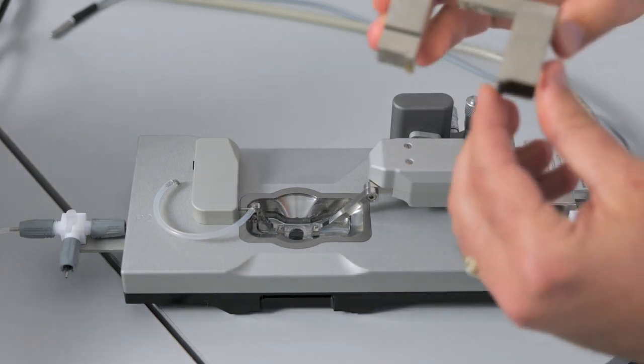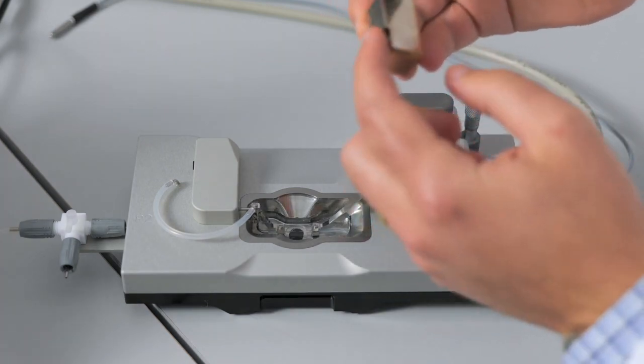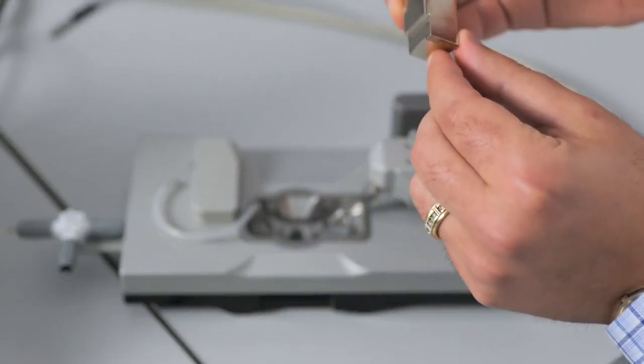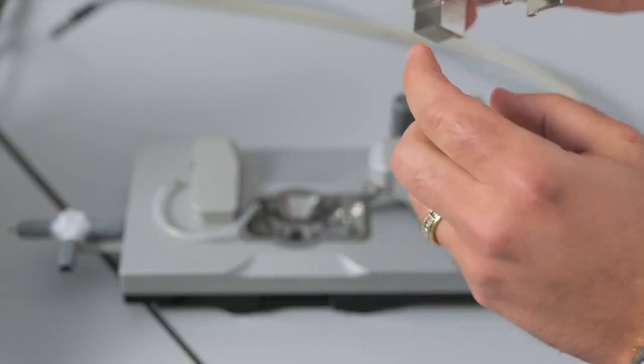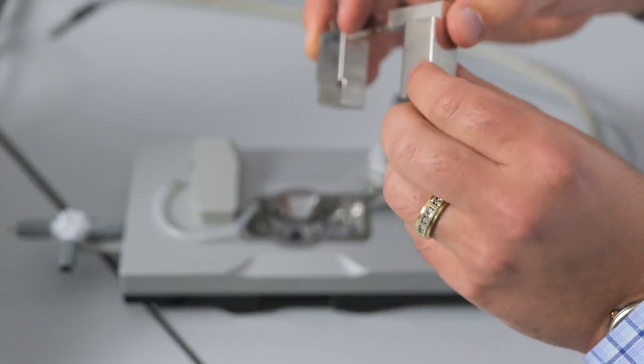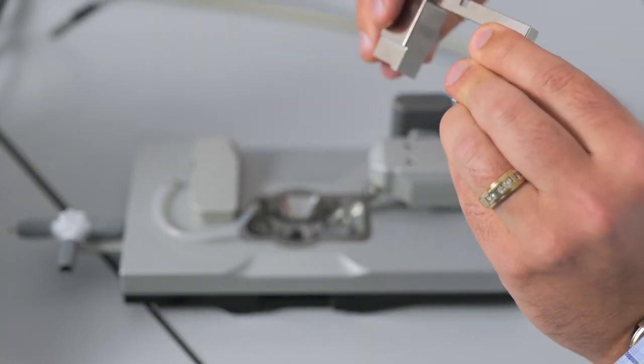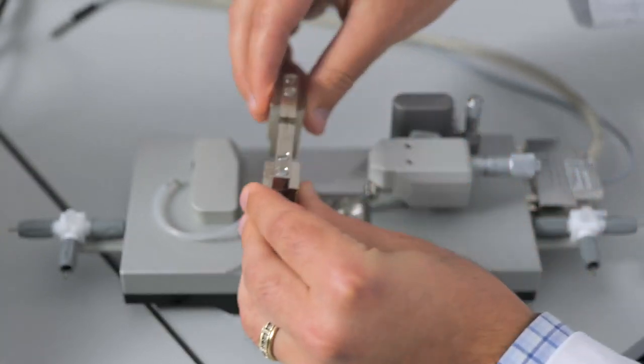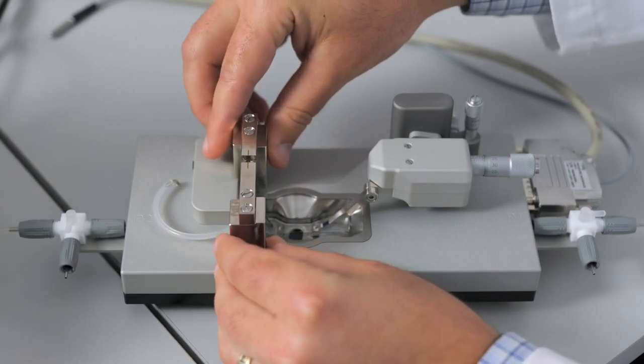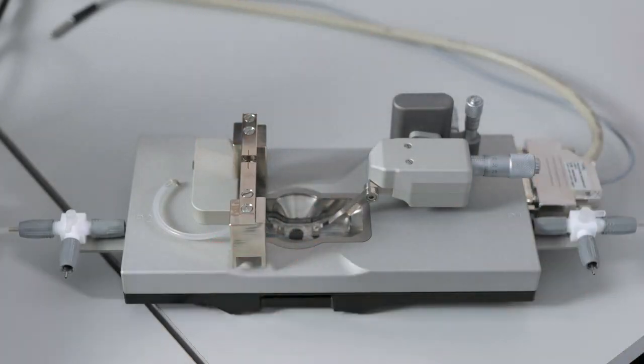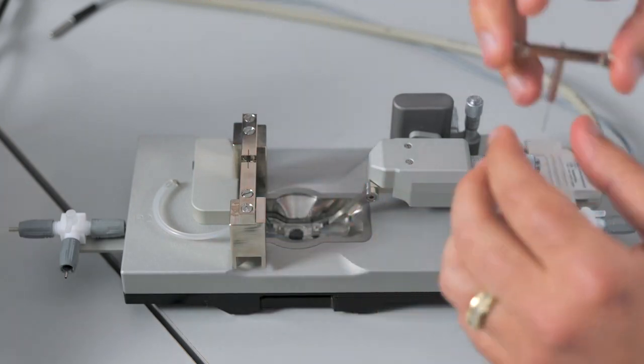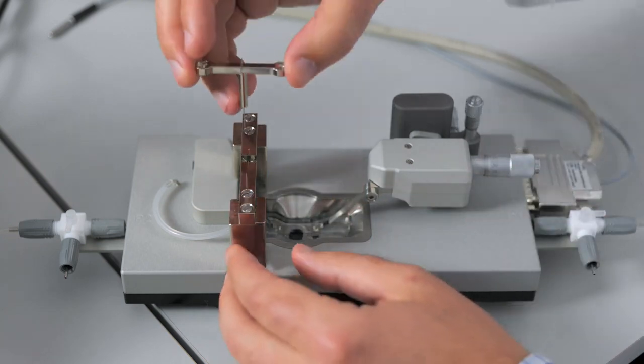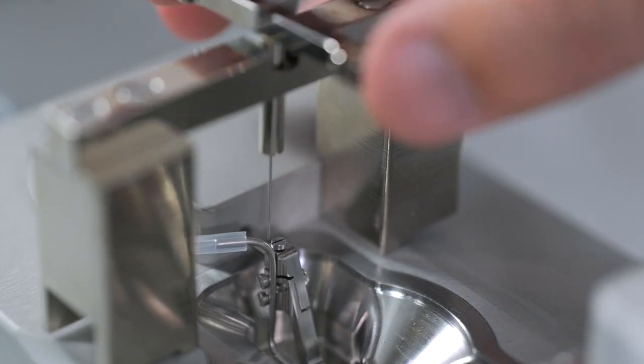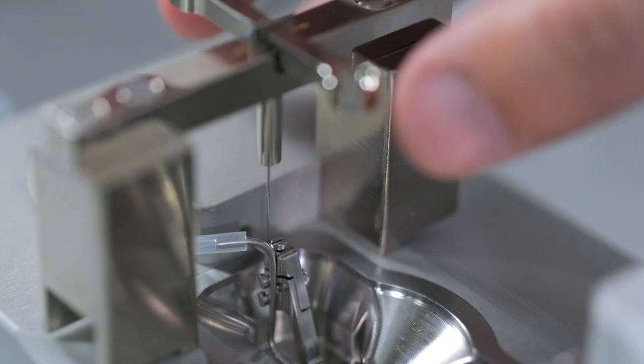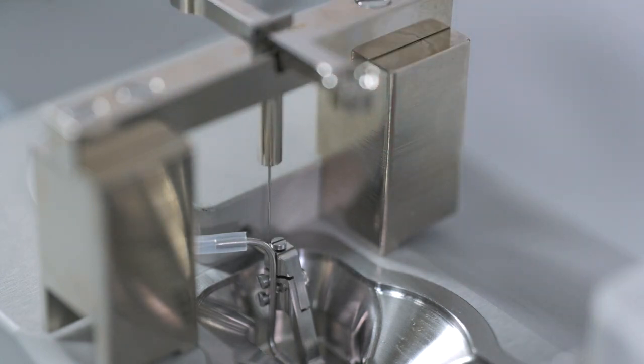You will see the calibration bridge has a unique design which should allow it to only fit one way on your chamber. This cutout on the side will go over the force transducer itself. Now you drop the T-balance in on the left side mount behind the screw. You want it to be as close as possible behind this mount without touching.